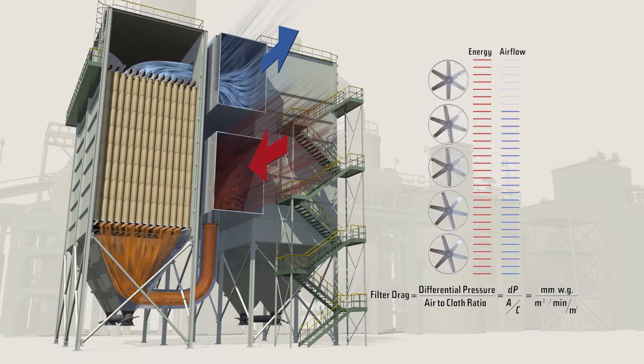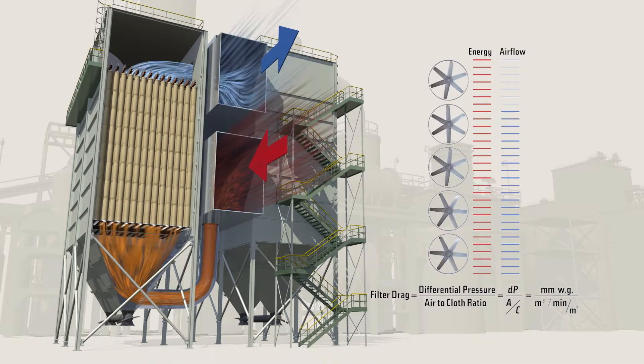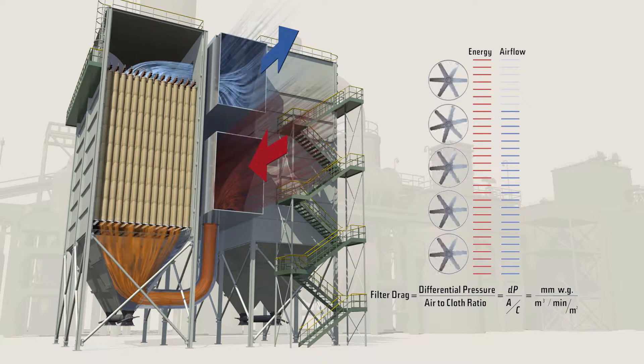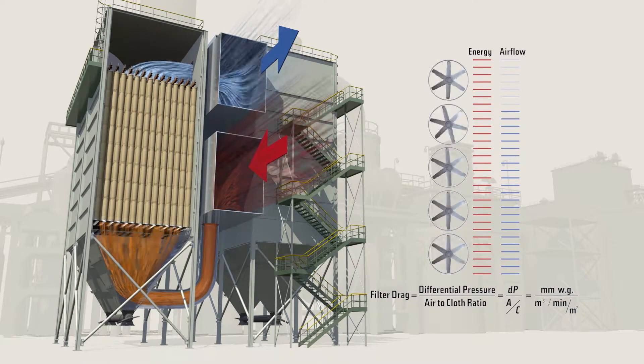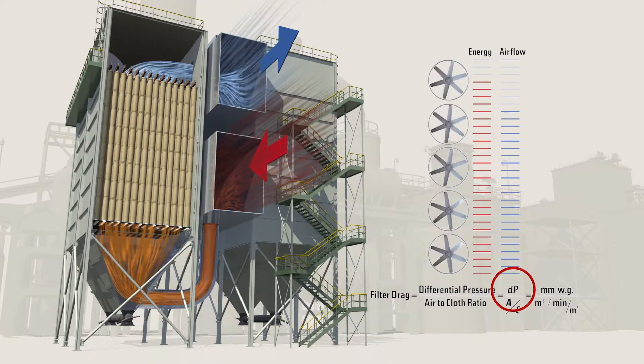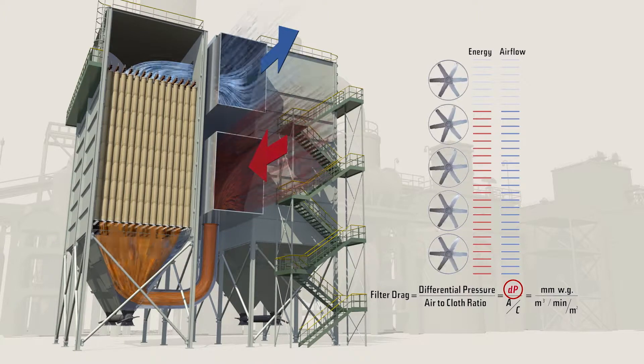On many baghouses, fan motors are variable frequency drive VFD equipped. Using Gore low-drag filter bags will allow the same airflow but operate at a 15% lower differential pressure. The fan motor could be operated at a lower speed and use less energy, saving you money.